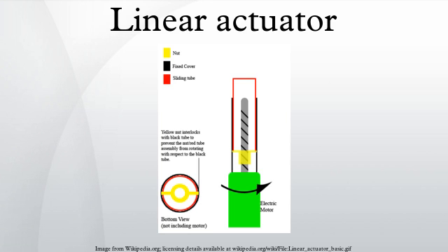In some applications, the use of a worm gear is common as this allows a smaller built-in dimension while still allowing great travel length. A traveling nut linear actuator has a motor that stays attached to one end of the lead screw, the motor spins the lead screw, and the lead nut is restrained from spinning so it travels up and down the lead screw. A traveling screw linear actuator has a lead screw that passes entirely through the motor. In a traveling screw linear actuator, the motor crawls up and down a lead screw that is restrained from spinning. The only spinning parts are inside the motor, and may not be visible from the outside. Some lead screws have multiple starts.